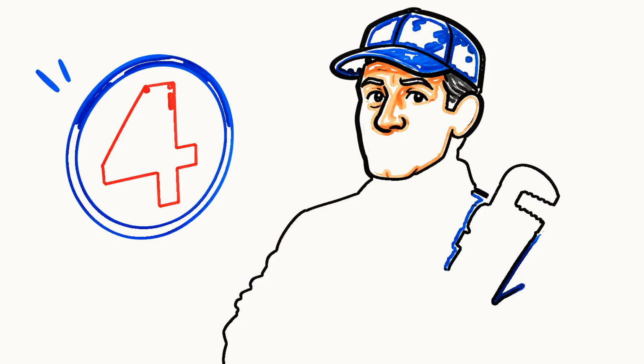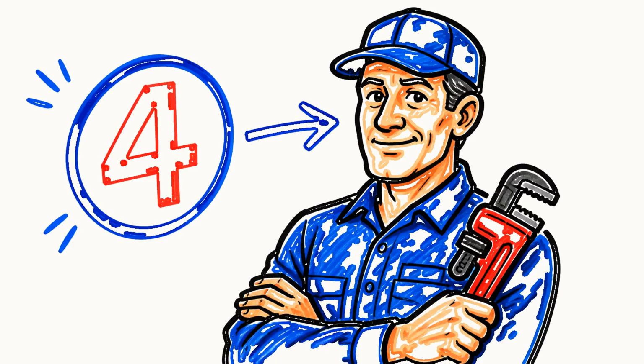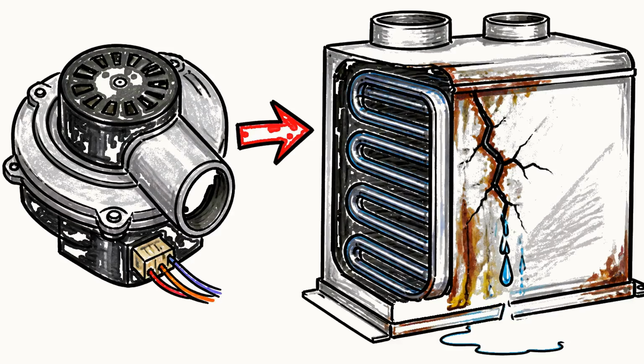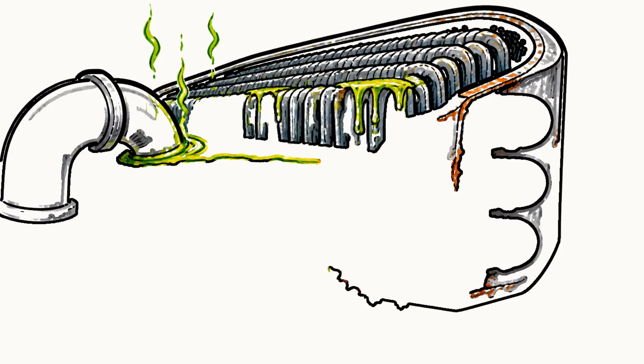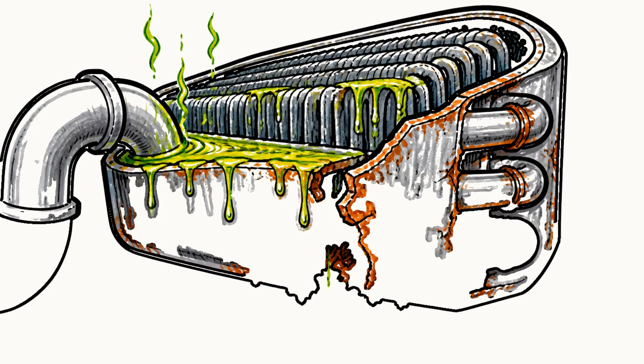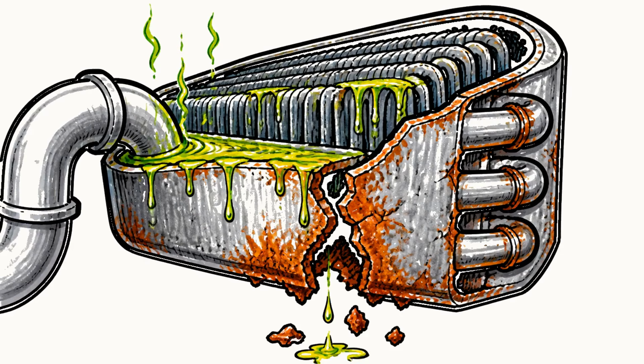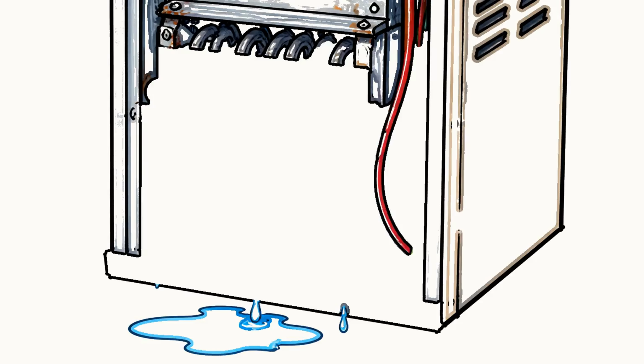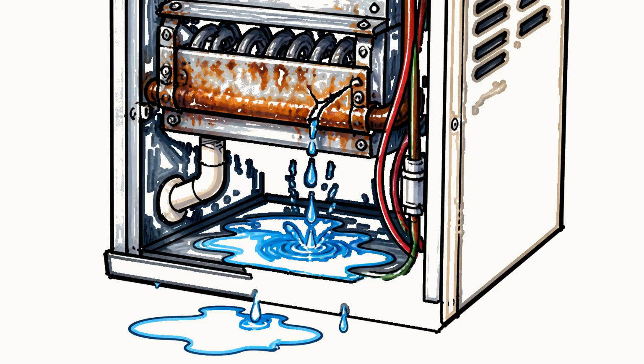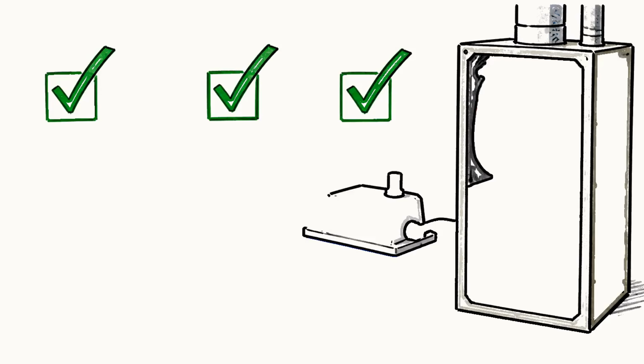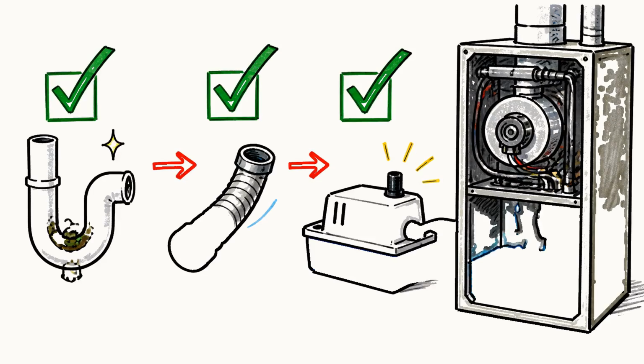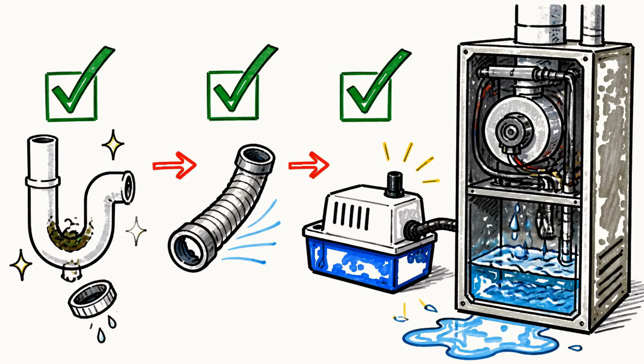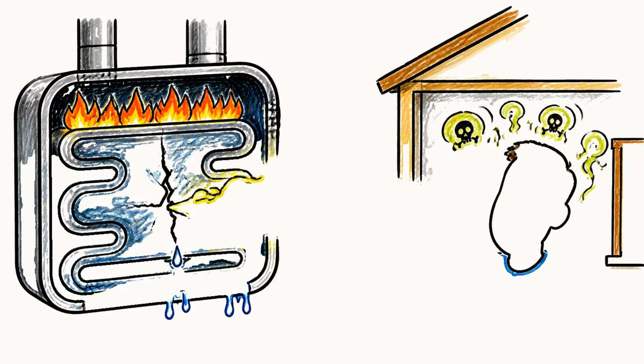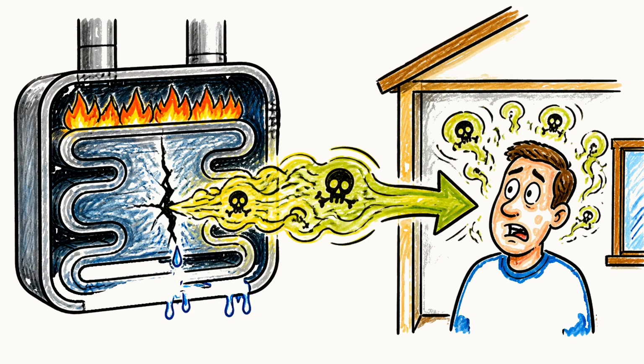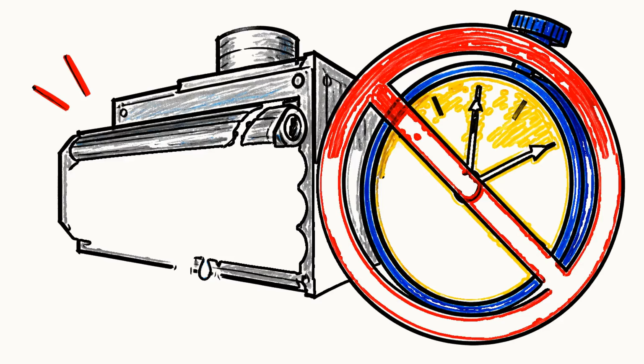The fourth cause is the one that actually needs a professional, and it is the cracked inducer assembly or secondary heat exchanger. All that acidic condensate spends years sitting against metal, and eventually it can rust or crack the parts it touches. When that happens, water escapes inside the cabinet even though your drain system is perfectly clear. The tell is simple. You clean the trap, the hose runs free, the pump works, and there is still water inside. At that point, it is time to call someone. A cracked heat exchanger does not just leak water, it can leak combustion gases, including carbon monoxide, into your air. So this is not a part to wait on.